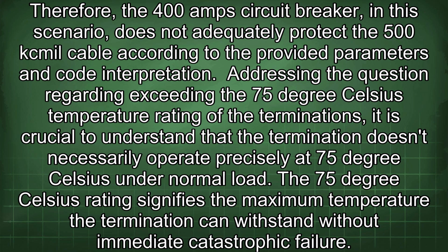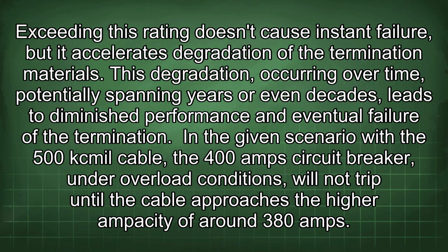Addressing the question regarding exceeding the 75 degrees Celsius temperature rating of the terminations, it is crucial to understand that the termination doesn't necessarily operate precisely at 75 degrees Celsius under normal load. The 75 degrees Celsius rating signifies the maximum temperature the termination can withstand without immediate catastrophic failure. Exceeding this rating doesn't cause instant failure, but it accelerates degradation of the termination materials.